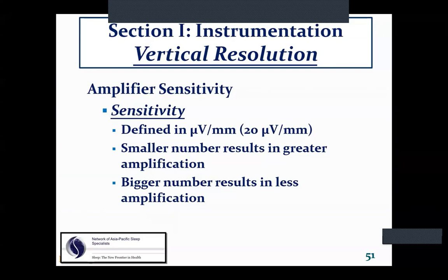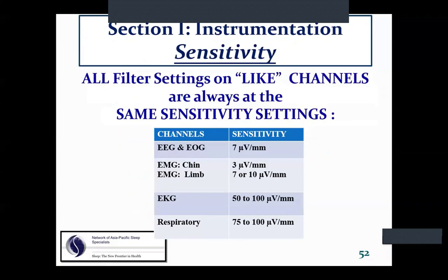So it's counterintuitive. A bigger number results in less amplification. So if I was using that 20 microvolts, and particularly in children, they have very high amplitude activity, I might want to turn the sensitivity up, which means a smaller number. So to get greater amplification, I might have said that backwards. So to get greater amplification, I'd go to 10 microvolts. So to get less amplification, I'd go to a bigger number, like 30. I think I did say that wrong. But correcting, a smaller number gives you greater amplification, and a bigger number results in less amplification. Again, all filter settings in like channels are always on the same sensitivity settings. And I've listed those that need to correlate together.